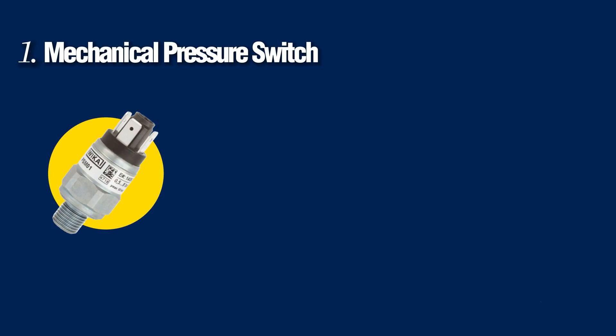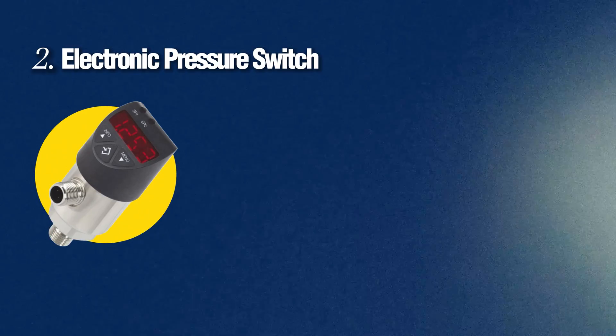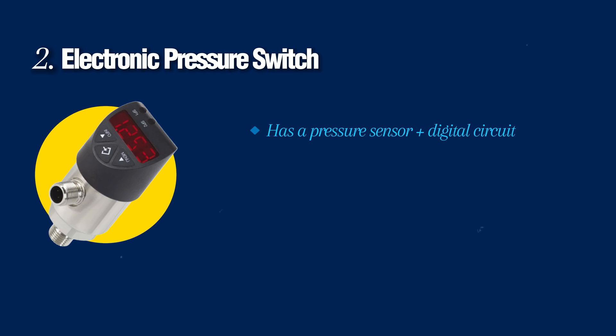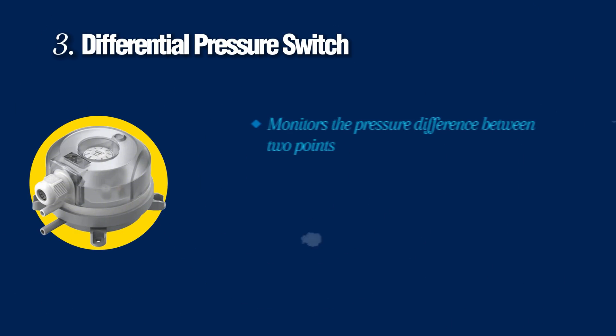Now let's cover the types of pressure switches. The first is the mechanical pressure switch — it uses a spring and diaphragm or piston, requires no power supply, and is widely used for simple on-off control. The second is the electronic pressure switch, which has a pressure sensor plus digital circuit, offering precise set points, delay timers, and digital display. It is widely used in modern smart automation systems.